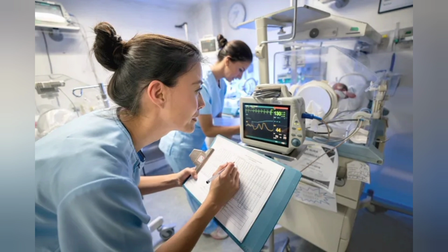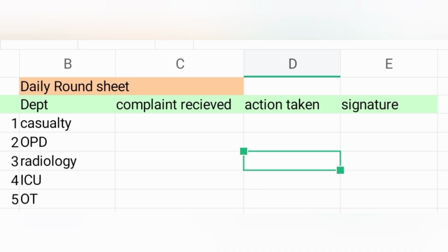Then the sixth file is the daily round register. Ideally, a biomedical engineer must take a daily round in every department of the hospital wherever medical equipment is being used. For that, you need to keep one register in which you should take the signature of the in-charge of that department. Note down complaints from the user on that day. That will not delay your service to medical equipment.